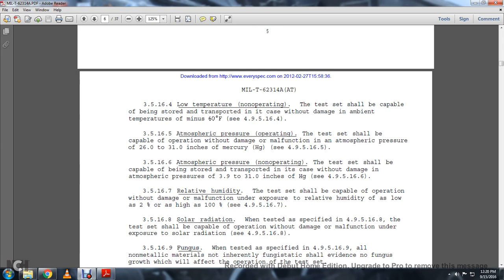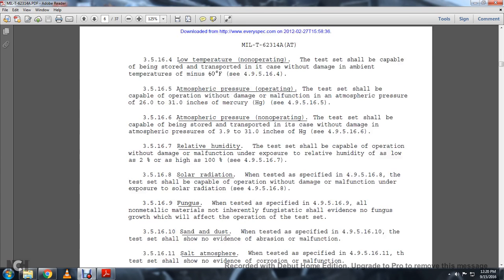3.5.16.7, relative humidity. The test should be capable of operating without damage or malfunctioning under the exposure to relative humidity as low as 2% or as high as 100%. 3.5.16.8, solar radiation. When testing specified by 4.9.5.16.8, the test should be capable of operating without damage or malfunction under the exposure to solar radiation.